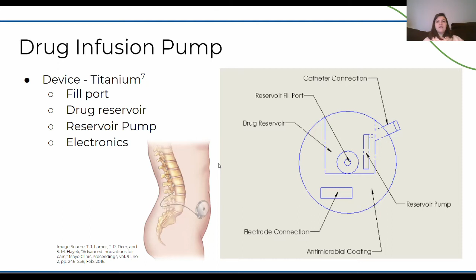There's a place for the electrodes to connect to deliver stimulation on the outside of the device so that the electrodes can be exchanged easily in a minimally invasive surgery. There's also an improved catheter connection to limit disconnections that uses a screw and latch mechanism. The catheter screws into the device like a typical catheter, and then a small latch is locked around it.